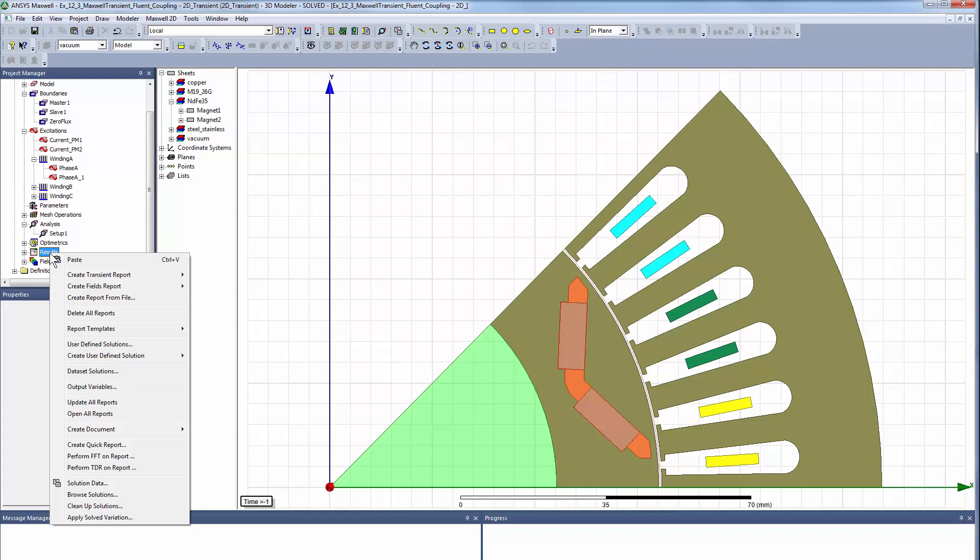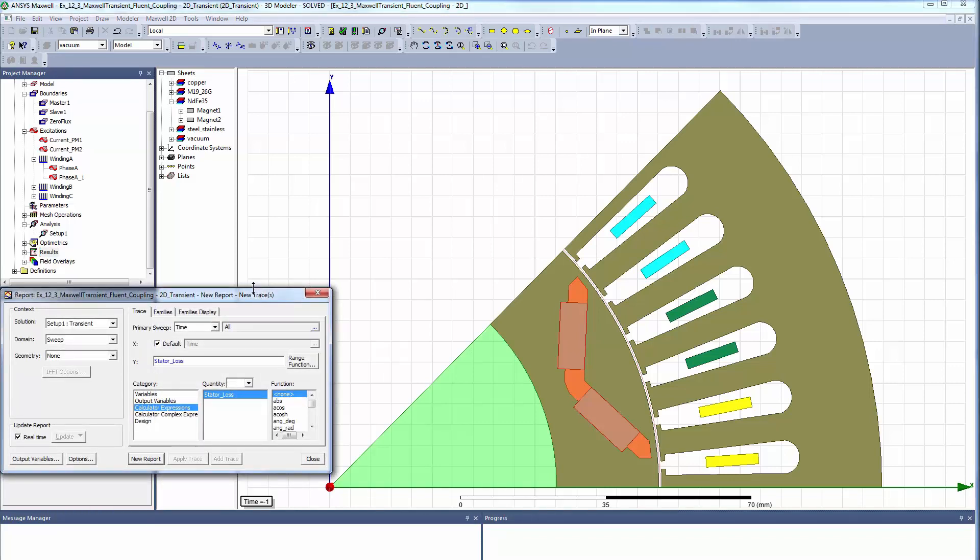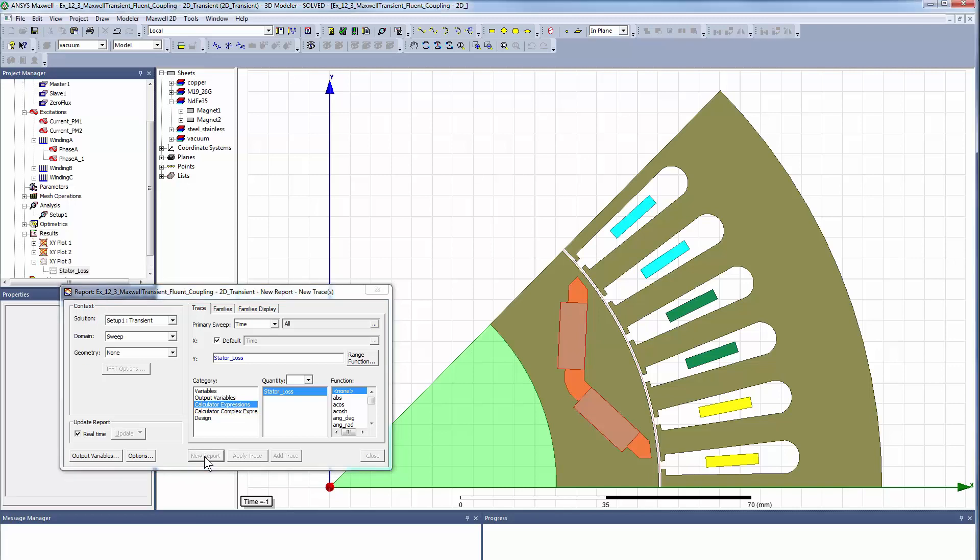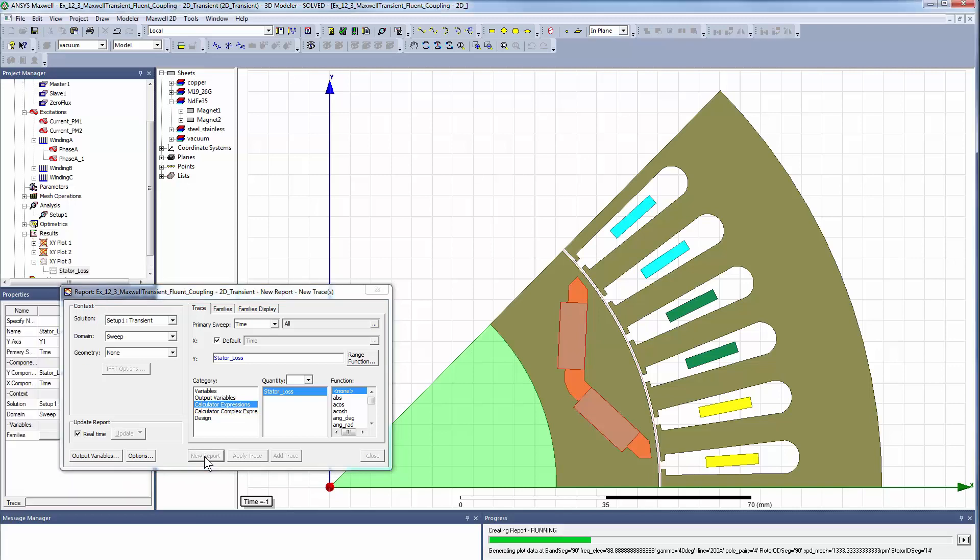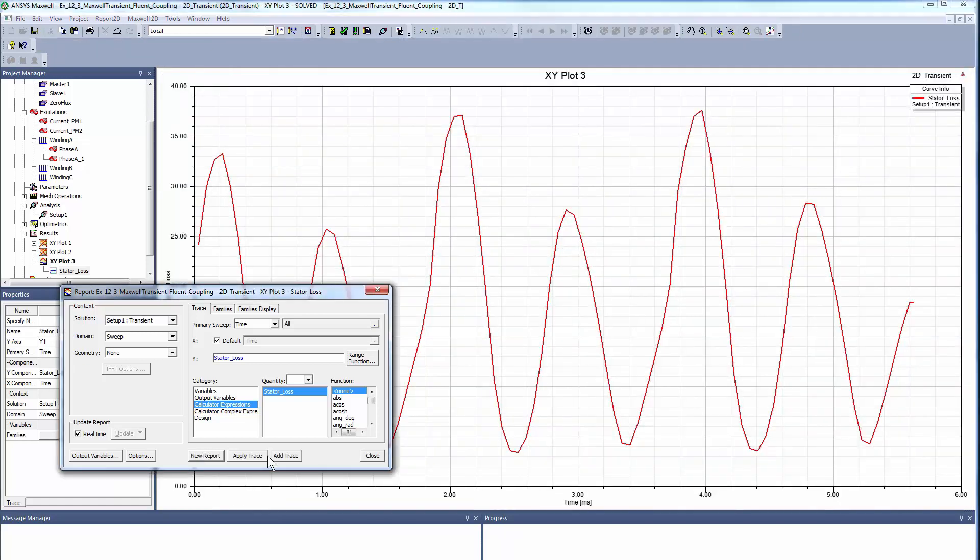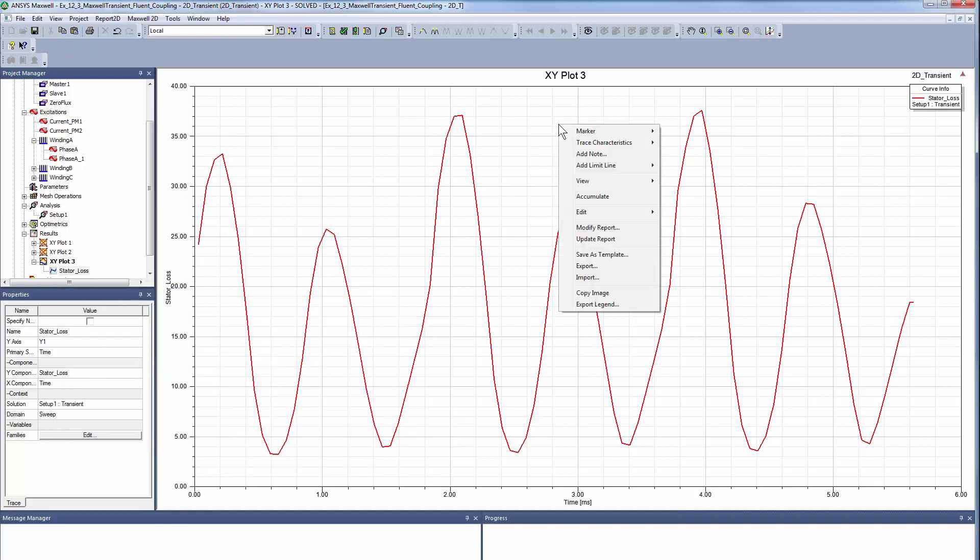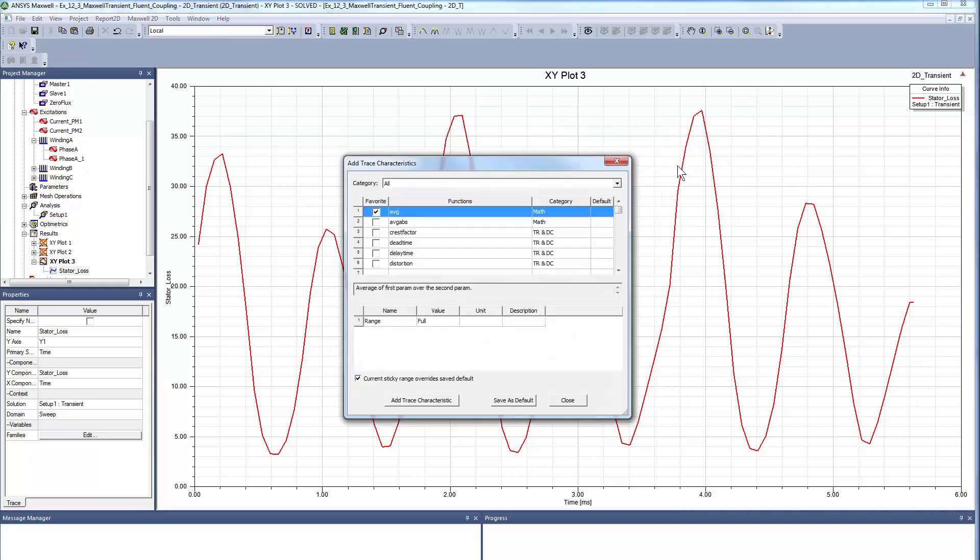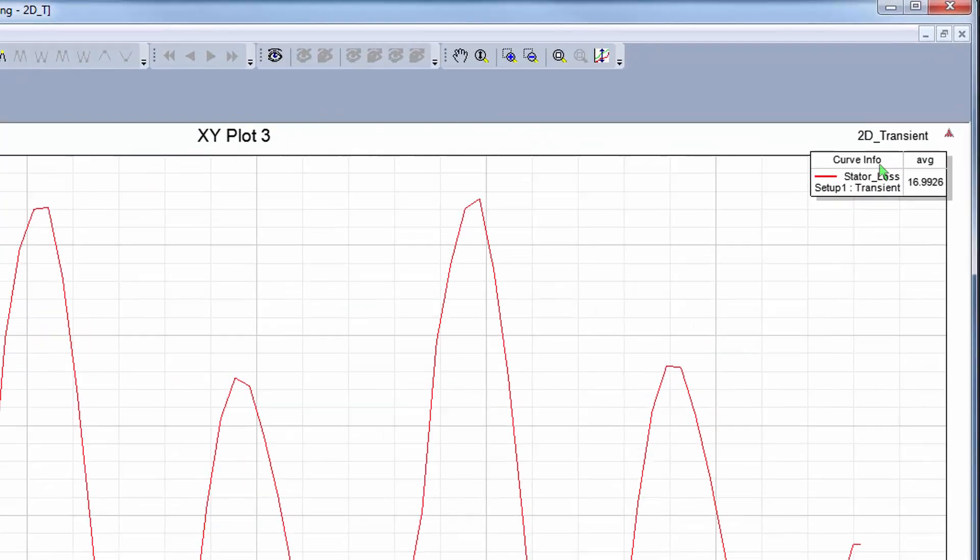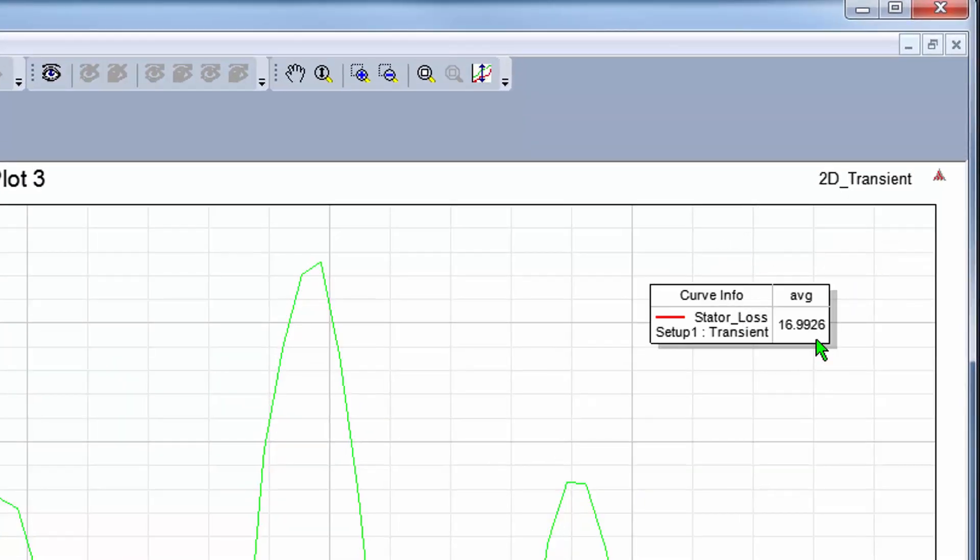The finite element solution is complete. We save fields, then go to the post-processor to create the stator and rotor loss based on the field's calculator expression. Here you see the variation of the stator loss during the transient simulation. We can compute the average from the trace characteristics over a full or specified range. This value will be compared with the value mapped into the CFD solver.